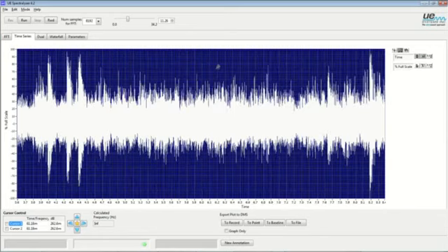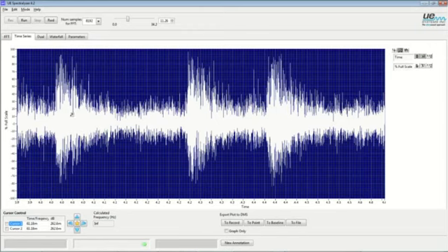And that's the key thing as well, because we talk about severity. How bad is something? With a tracking event, my experience has shown the worse that a tracking event becomes, the more frequently the discharges of energy are taking place in the insulating system, and they become more compacted in here. We can see an example of that to the left. There are many discharges right here in a very short period of time, happening at different points in time. So the length of the discharges are longer periods, and they are more frequent throughout the recording. This is a key indicator that the fault is getting worse.